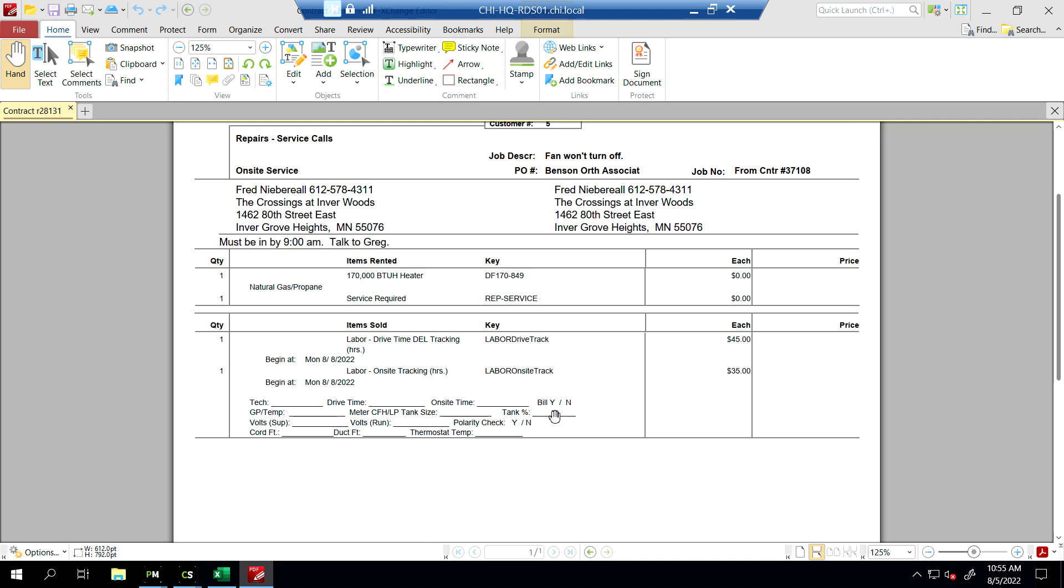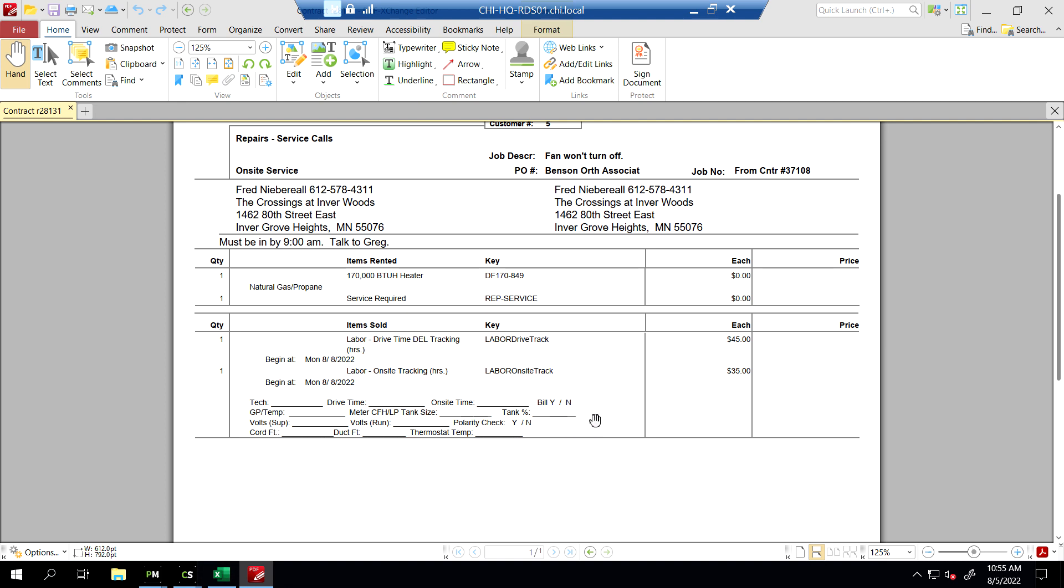Tank percentage. I always look at the gauge on the tank. Make sure we're a minimum of 25% at all times in the tank for it to really get to the BTUs where you need to get to. As it gets colder, you get less vaporization on these tanks. So go ahead and check your vaporization charts to see what that percentage equals for BTUs. So in this case, just put in whatever percentage is - 45% the tank was. It was a 500 gallon tank.